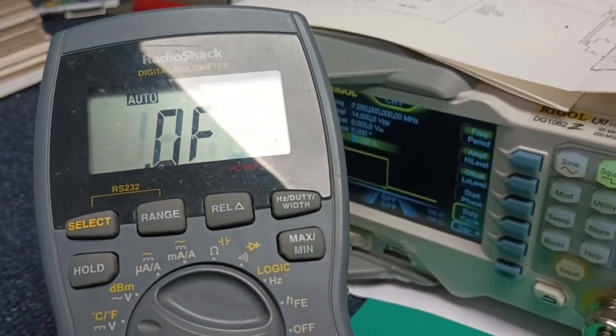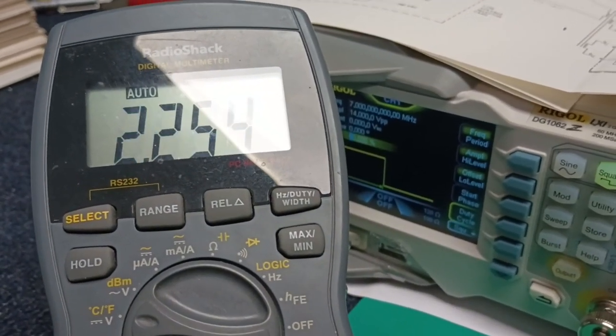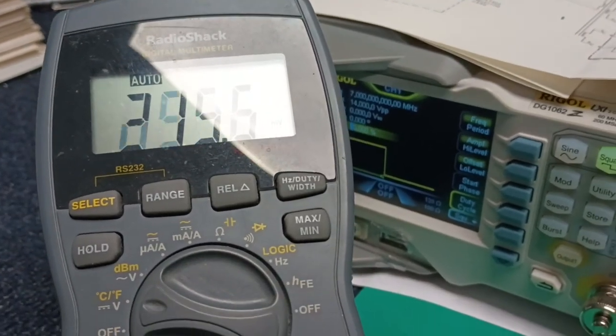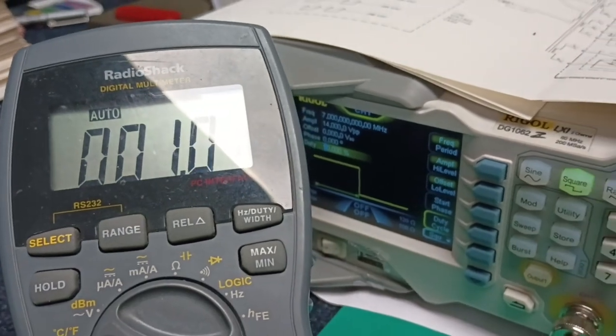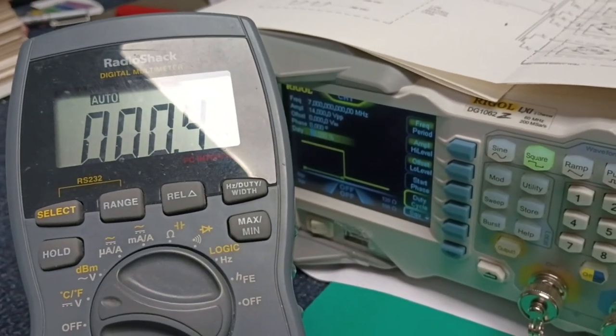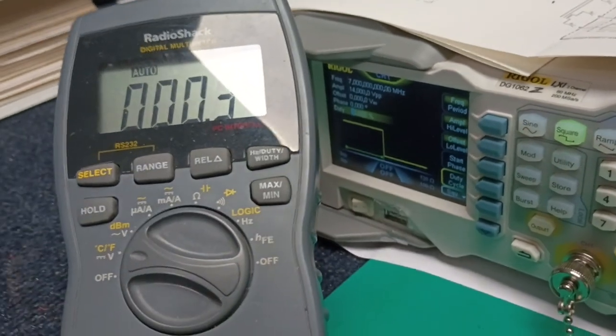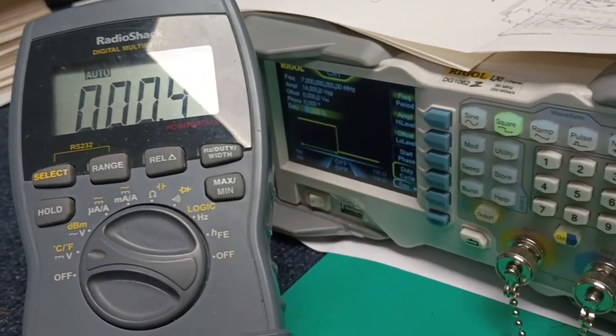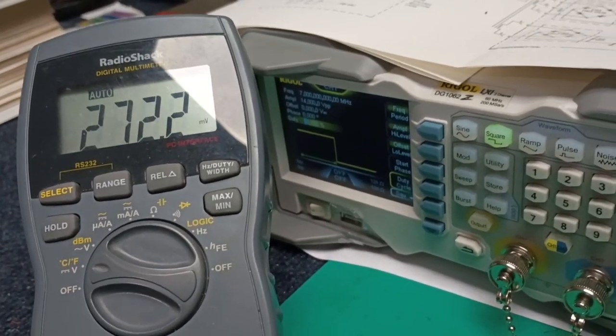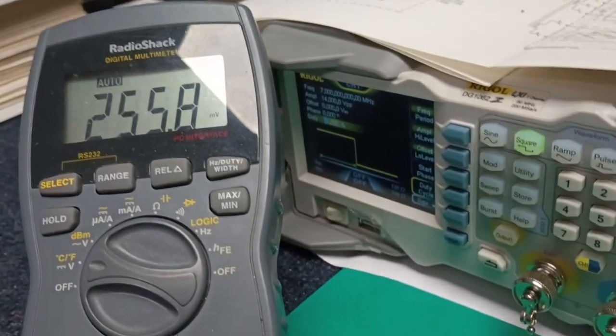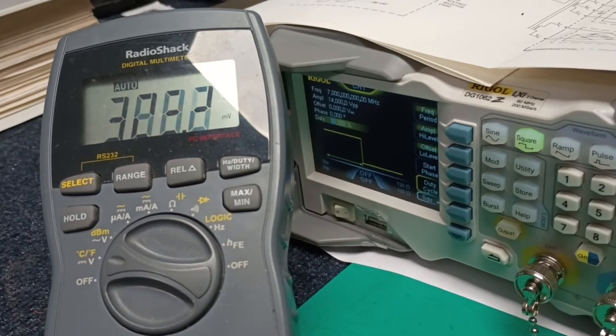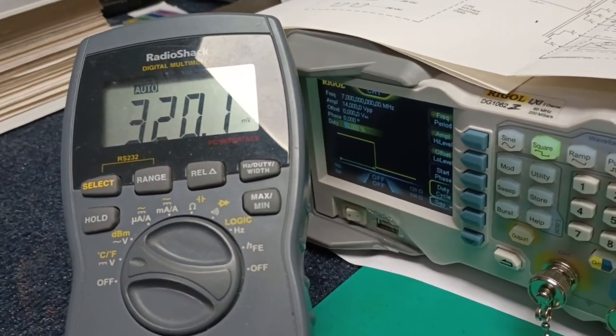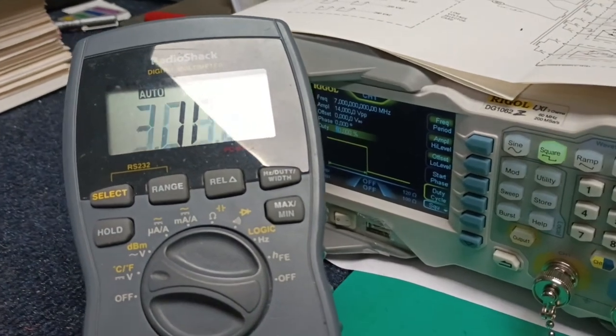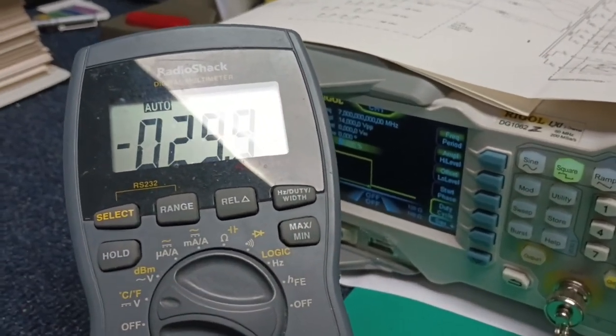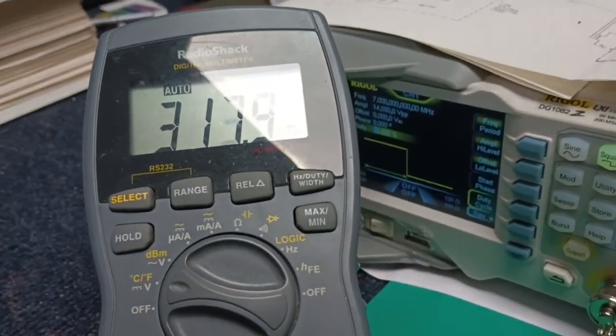And on that supply, there's its so-called ground terminal, and there's its neutral terminal. Isn't that interesting? All that jumpy voltage went away, and the line terminal L1 reads some strange thing. And notice it's reading the same strange thing as this minus terminal from the DC power supply. That's a warning. Be very careful. The fourth power supply, similar thing.